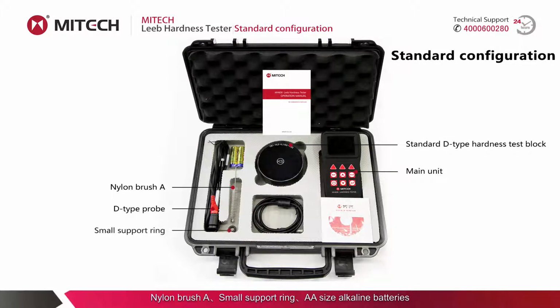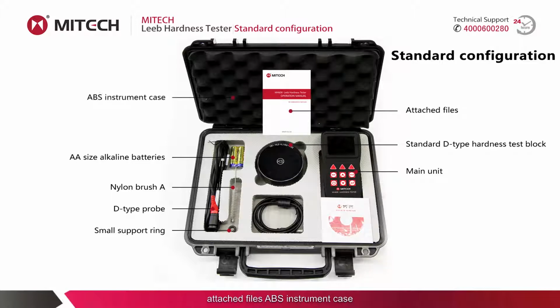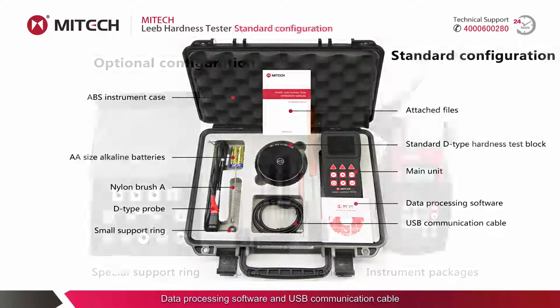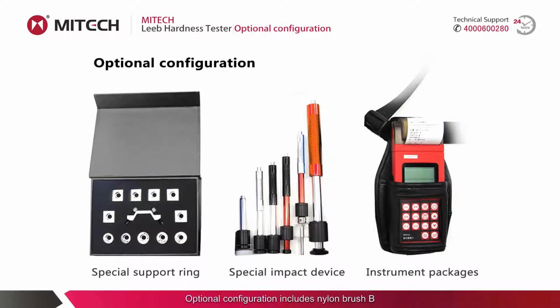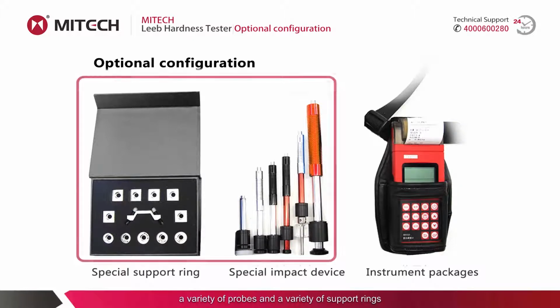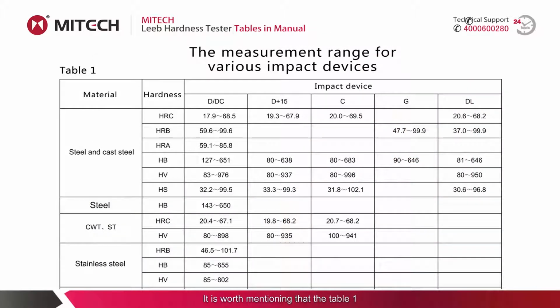A, small support ring, AA size alkaline batteries, attached files, ABS instrument case, data processing software, and USB communication cable. Optional configuration includes nylon brush B, a variety of probes and a variety of support rings, instrument packages, and so on. It is worth mentioning that Table 1 of the Mitech Hardness Tester Manual lists the detailed measurement range. As shown in the table, use a D or DC probe to measure the HRC Rockwell value of steel and cast steel. The measuring range of the D or DC probe for steel and cast steel is 17.9 to 68.5 HRC.